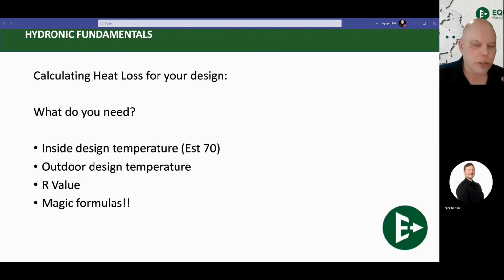So that's the start. That's the basics. These are a couple pieces with regards to the code and the details that you need to know. Now, we get into the fun stuff. I talked a little bit about heat loss and that system design. Your boiler has to be sized to the heat loss. The design's got to be done to calculate heat loss. How is the heat loss even done? What exactly is it? What you need in order to conduct it is your designed inside design temperature, which you can find in the building code for various cities that you are in. Usually the inside design temperature is going to be 70 or 72.